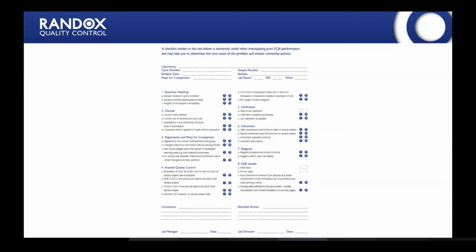What we also would recommend is that for every individual sample, instead of just looking at those results which are poor, you review basically everything, because you can have the start of the development of trends or sudden shifts in performance that are not necessarily falling outside of your limits, but may be the start of poor performance, or certainly a shift in performance.